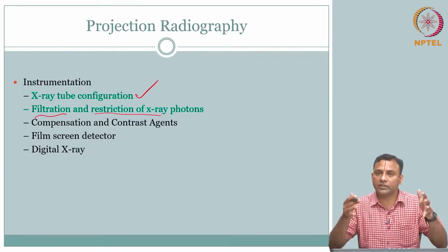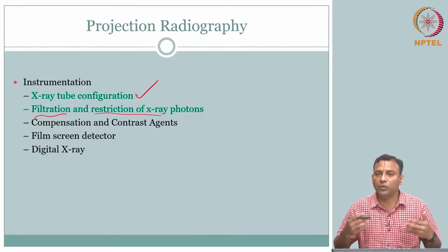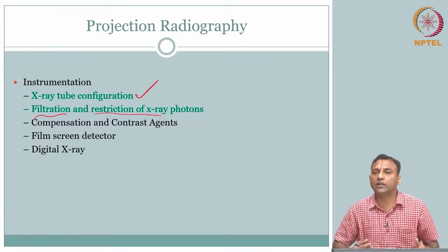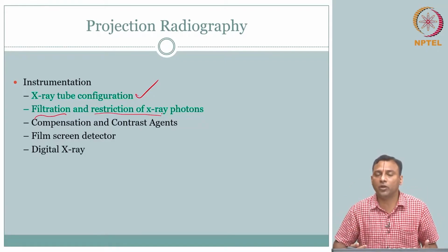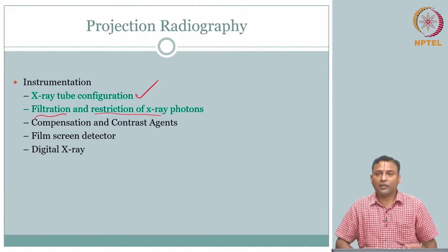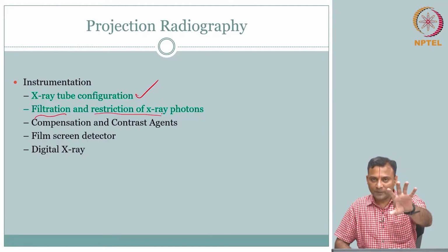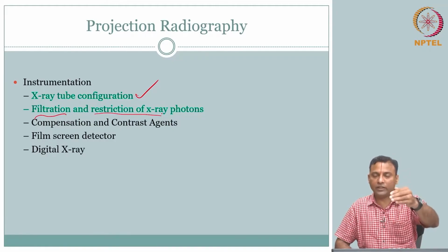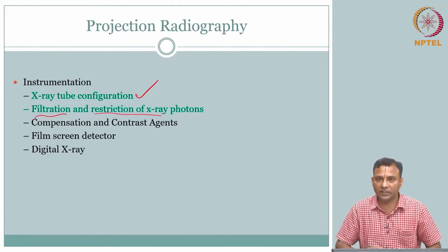What is restriction? It is just to cover the field of view. You do not want to send the X-rays to regions that are not going to be part of the imaging, so as to avoid dosing the patient. Okay. So, after that, we had the source part. Just outside the source we talked about filtration, restriction.